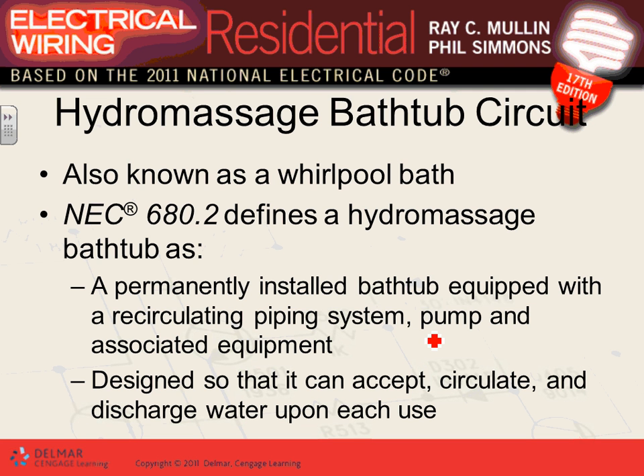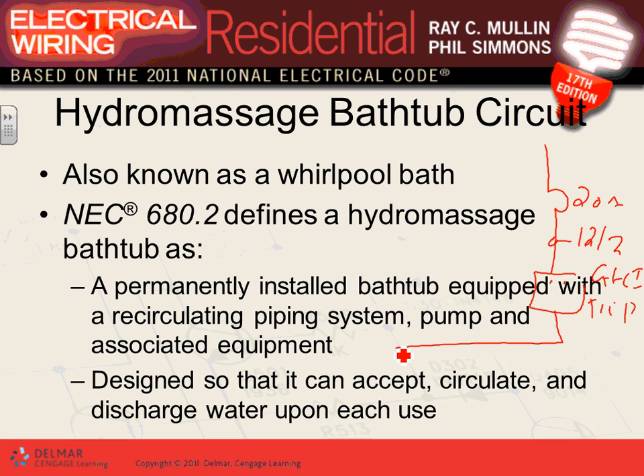Okay, hydro massage bathtub. Hydro massage bathtub, very simple, very easy. What you do is you bring a dedicated, typically 20 amp circuit with a 12-2. You bring it into a GFCI trip, and you come into a receptacle, and then your pump is here, and you plug your pump into this receptacle. That's your hydro massage bathtub. That's a typical wiring method for a hydro massage bathtub.